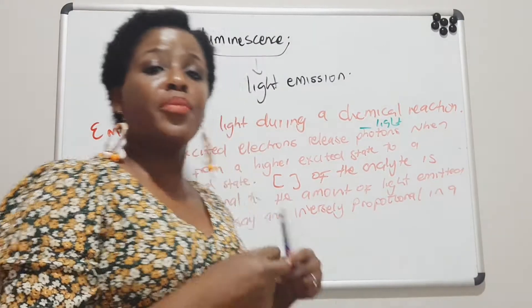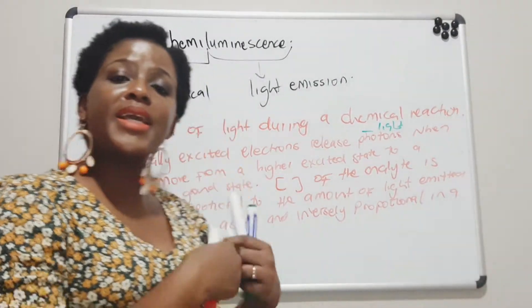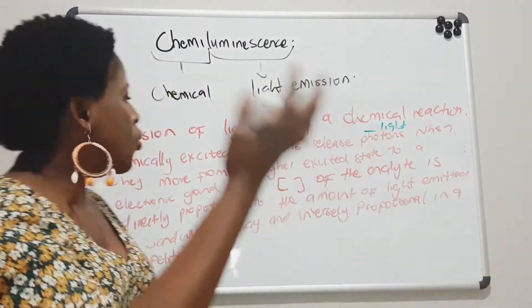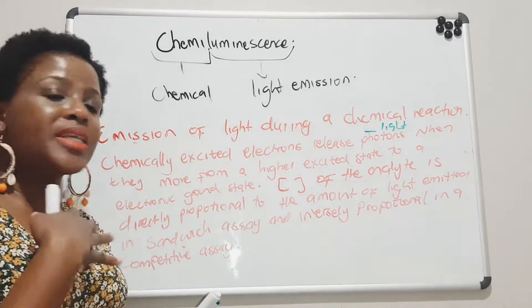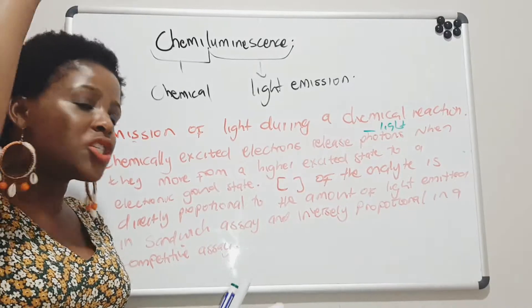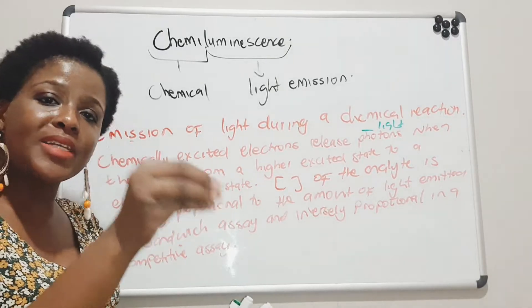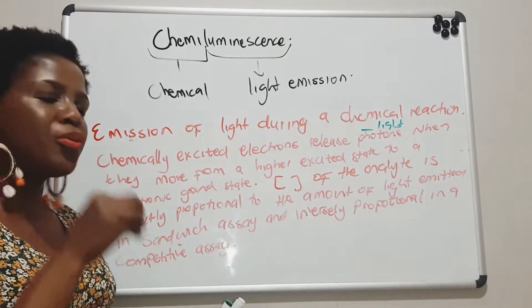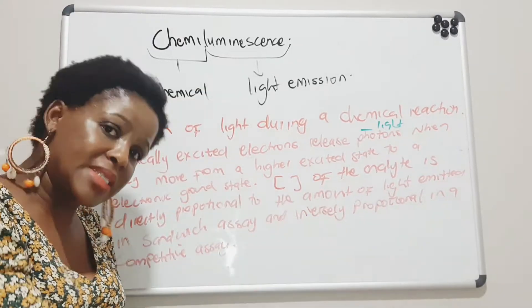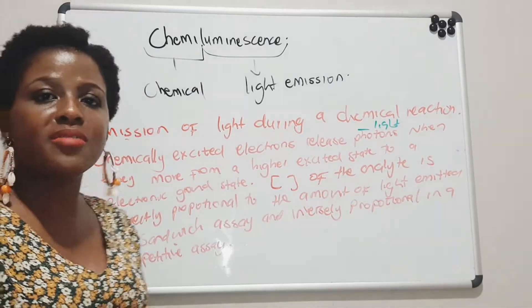To recap — in chemiluminescence there is the emission of light during the course of a chemical reaction, whereby chemically excited electrons release photons when they move from their higher energy state into their electronic ground state. The concentration of the analyte is directly proportional to the light emitted in a sandwich assay, and inversely proportional in a competitive assay.